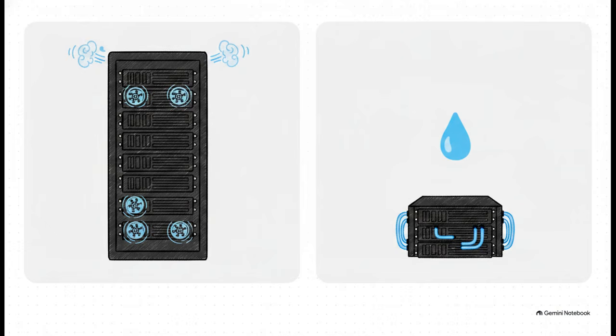To really visualize how that SUE metric is achieved, let's look at the old format versus the new. To hit a specific performance mark, an air-cooled system needs a massive 10U server. The exact equivalent in a liquid-cooled system? Just 4U. That's a space ratio of 40%, leaving you with 60% more room in your racks. It's a stunning visual representation of efficiency.